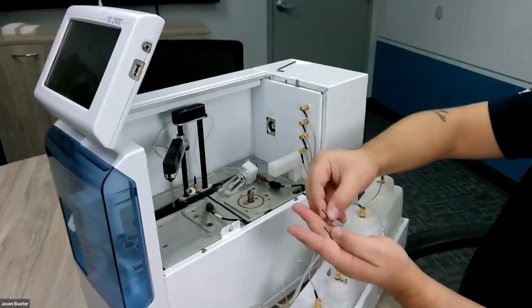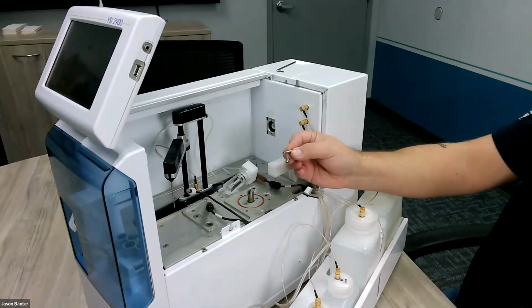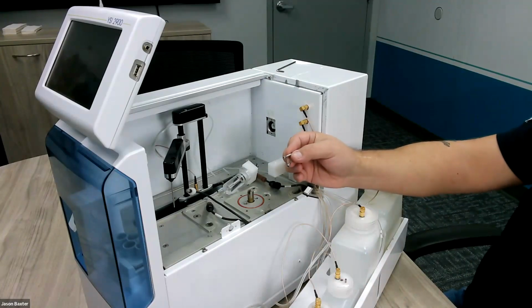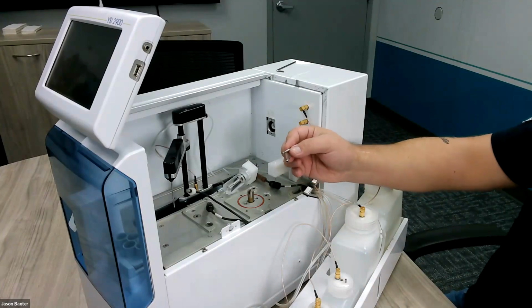One thing to note is these 2 bolts for the sipper pump assembly are slightly different length than the 3 bolts that are used for the waste chamber. So when you set them aside, make sure you put them into 2 different groupings. Make reassembly a little bit easier. Oops, I'm terribly sorry for that. Had an earthquake here.